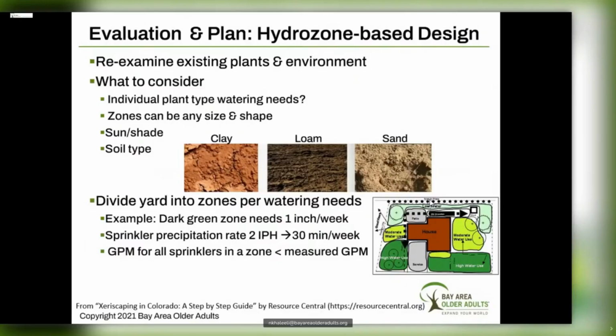The measured water pressure is important because pressure determines the spacing between sprinklers. The rule to remember is that the water pressure at the head must exceed the distance between the heads. If the pressure is 20 psi, heads cannot be placed 25 feet apart. You need a pressure of at least 25 psi or more to go the distance of 25 feet.